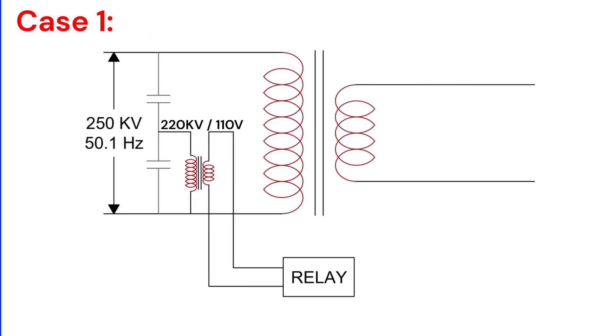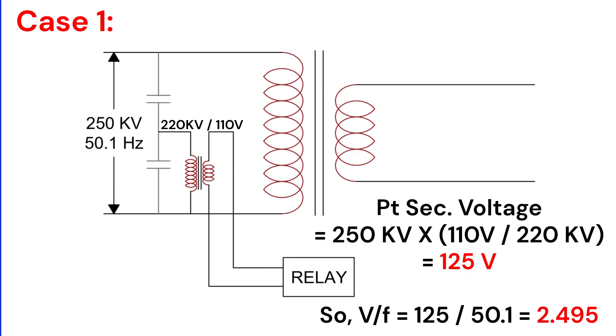Let's look at two scenarios. Case 1: The primary voltage rises to 250 kV, and the frequency is 50.1 hertz. The PT secondary voltage becomes 125 volts, so the V/F ratio will be 125 divided by 50.1, which equals approximately 2.495. Since this exceeds our set limit of 2.42, the relay will pick up and trip after some time.